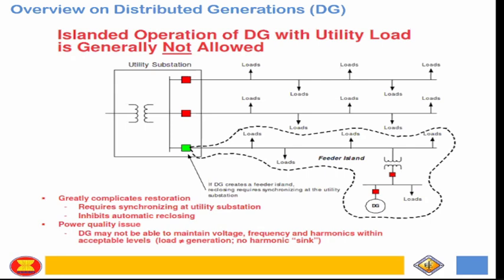But if the tendency is that the generation supplying the grid is larger, then you somehow release the load, or what we call load rejection. In a normal condition, that load is being compensated by the excitation system, which supplies and compensates the load impedance. When it's isolated, the internal voltage of the generator will rise.